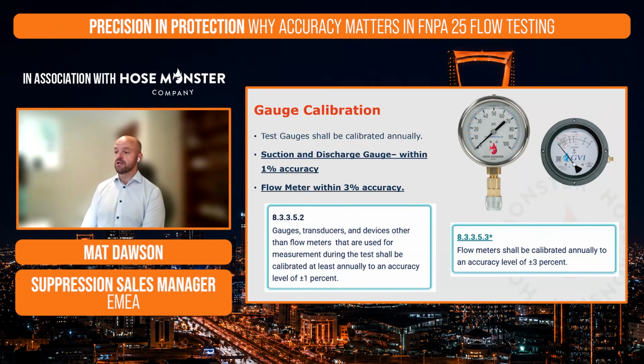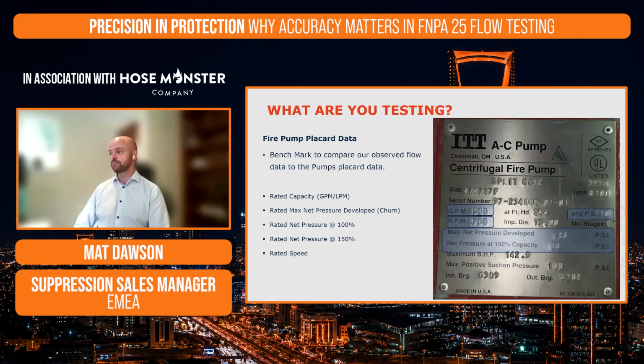It is worth noting that if you use any other gauges that we don't supply, all gauges have a tolerance. So you might be replacing gauges. Just make sure that the tolerance is the accuracy that is required. So again, 1% for the suction and discharge, and 3% for the flow meter. We obviously have calibration services. You can use any calibration house as long as they're certified. Again, as Patrick said, speak to other manufacturers if you need to, but the main thing is that the gauges are calibrated annually. Great, thanks, Matt.